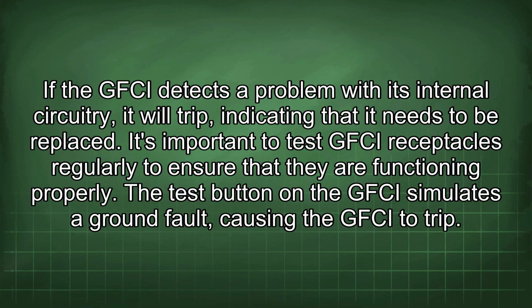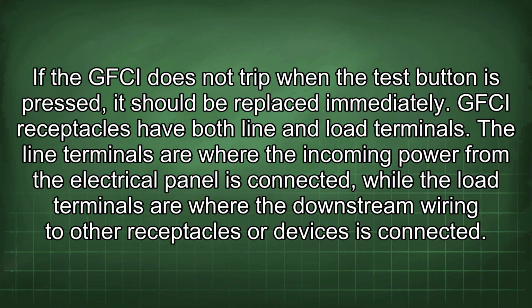It's important to test GFCI receptacles regularly to ensure that they are functioning properly. The test button on the GFCI simulates a ground fault, causing the GFCI to trip. If the GFCI does not trip when the test button is pressed, it should be replaced immediately.